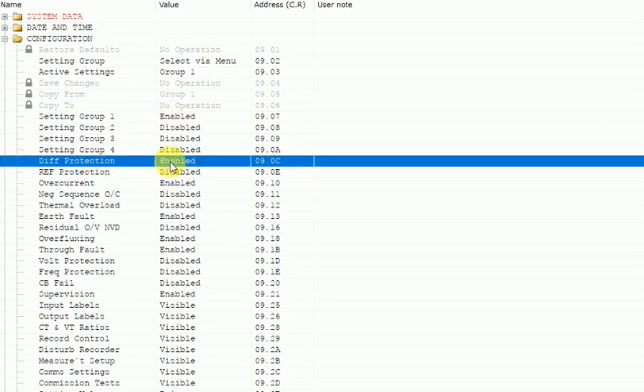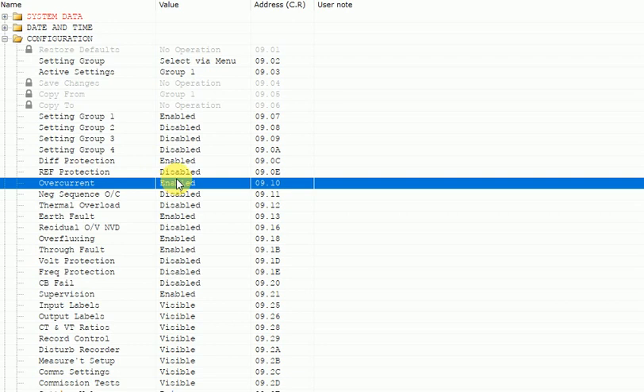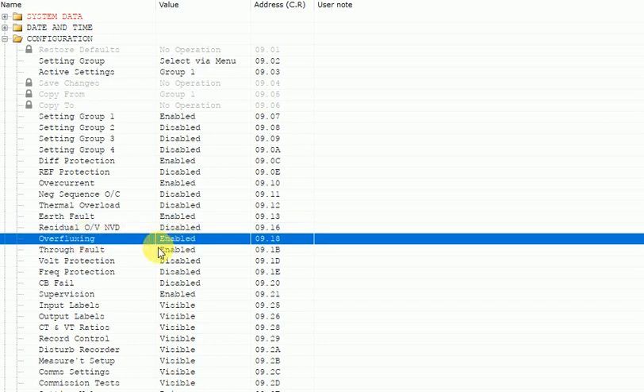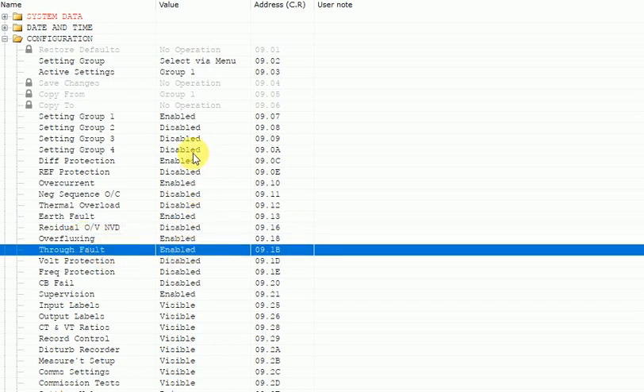Here we are using this relay for differential protection, so make it enabled and make the others disabled. I have also enabled earth fault protection and over-fluxing protection. Whatever protection you want to use, make it enabled. At the bottom, those settings will be visible only if enabled; if disabled, the setting parameters are not visible.